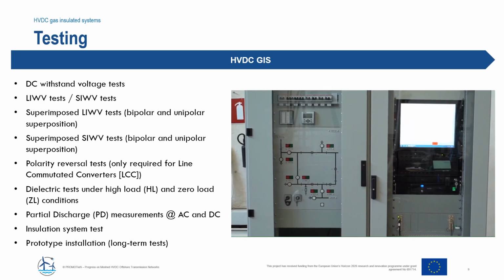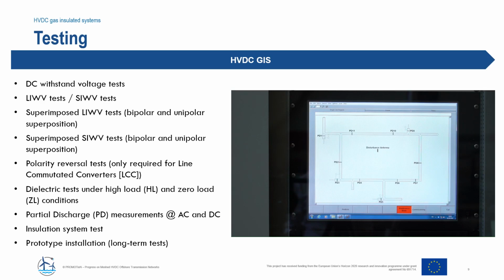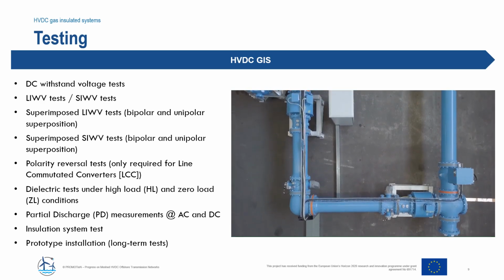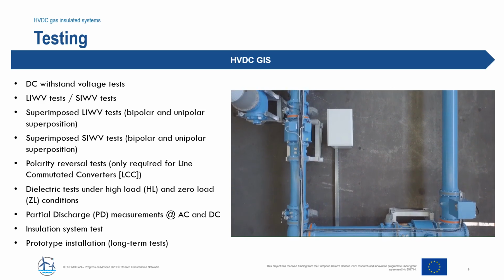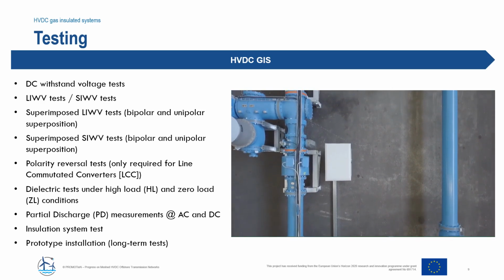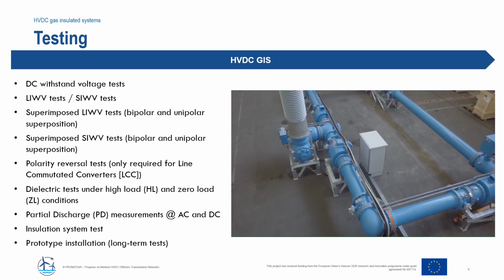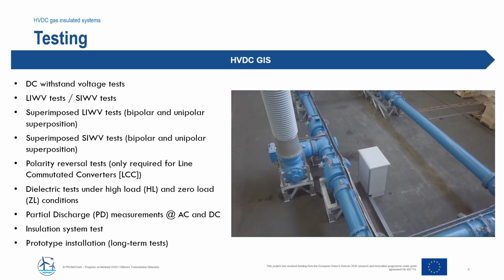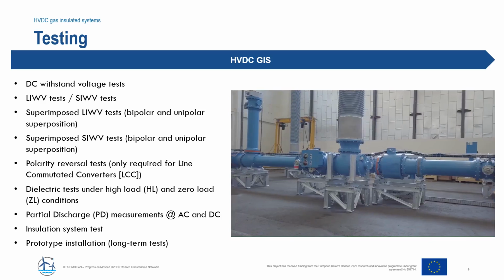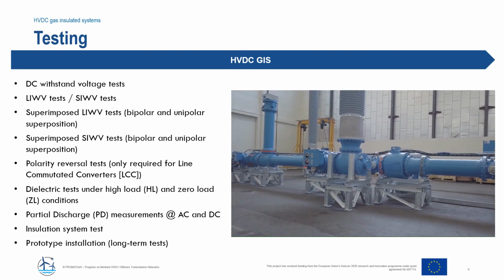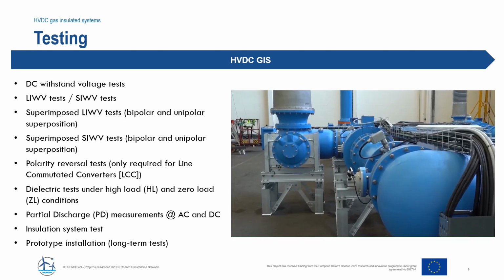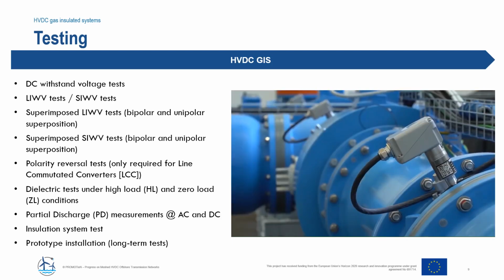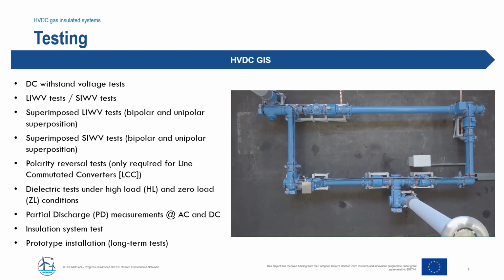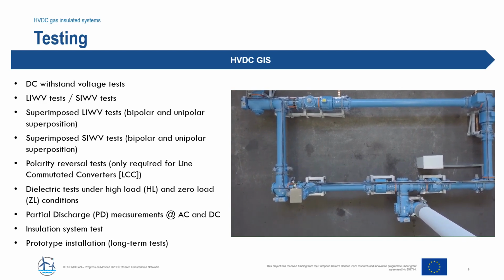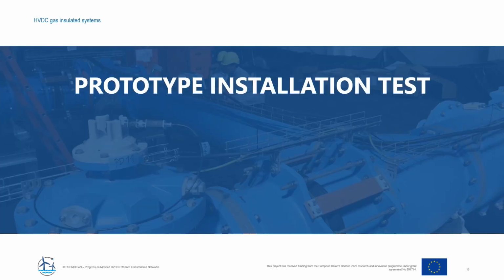There was also a demand from users and regulators for a full-scale demonstration of the technology readiness level of HVDC GIS. Such a full-scale demonstration, also called prototype installation test, was specified and executed as part of the promotion project. The 1.5-year-long test is now finished and verifies the overall performance of the manufacturer to produce and install HVDC GIS. Now Michael and Nadew will give more details about the prototype installation test.